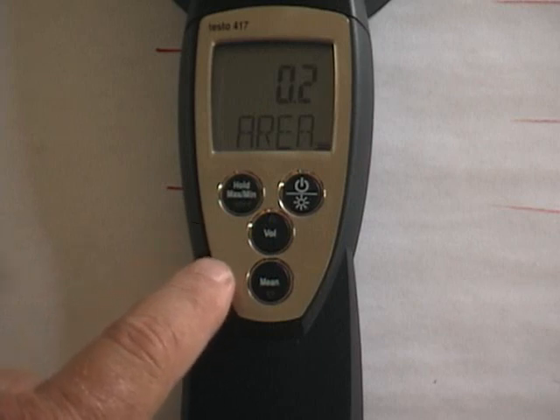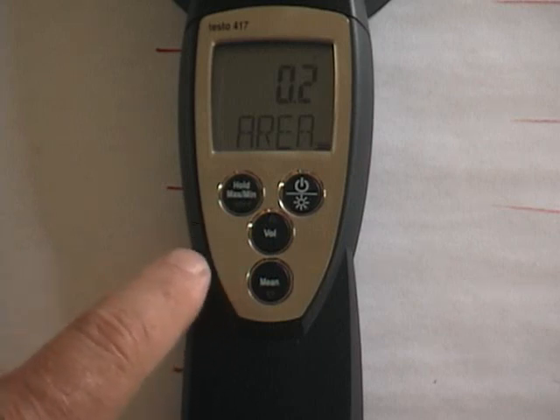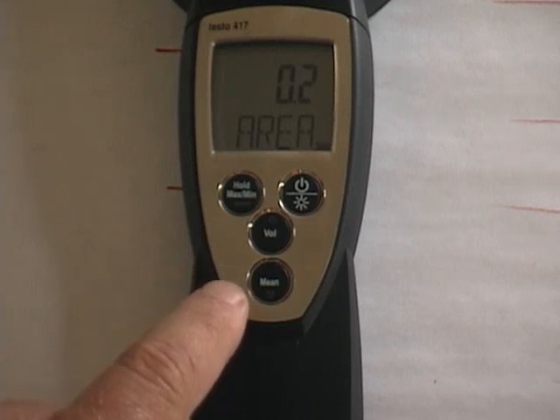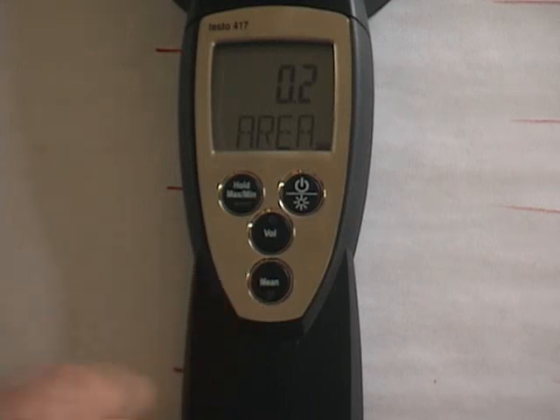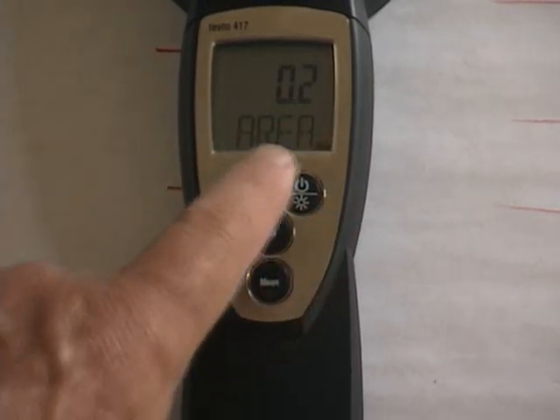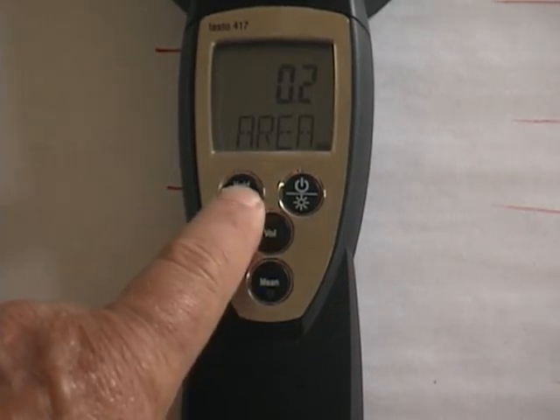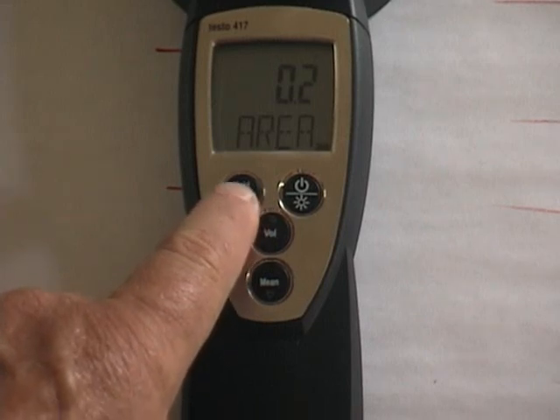We're going to get area. This is your input if you want to input the square inches of open area on your return grill and automatically calculate CFM. We're not going to use that, so we've got that set at the lowest setting so we don't get confused reading CFM instead of feet per minute.